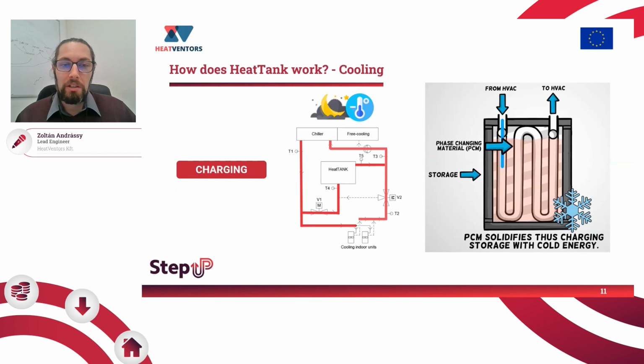Let's see, in a schematic, how it works. We have the chiller, we have the cooling indoor units. What happens without the heat tank: 7 degrees goes as a supply to the cooling indoor units, and 12 degrees comes back to the chillers. This circulation is ongoing. With the heat tank, if we open the V1 valve, we are able to circulate the 7-degree colder fluid through the heat tank. The material inside the heat tank solidifies. Let's say that the material has the melting or solidification point at 9-10 degrees, so it is able to solidify.